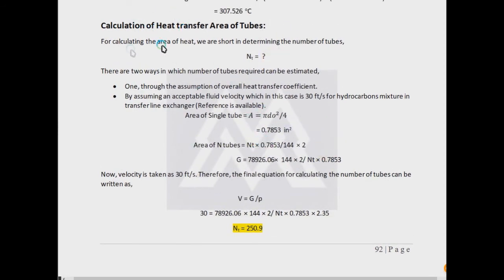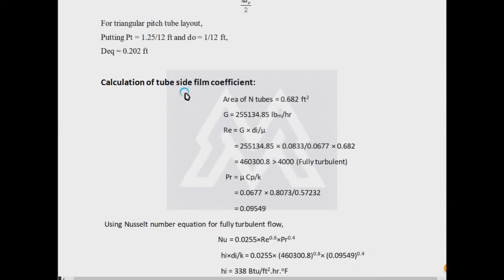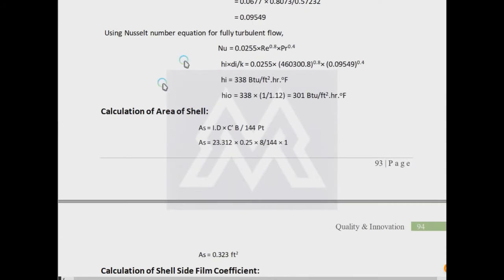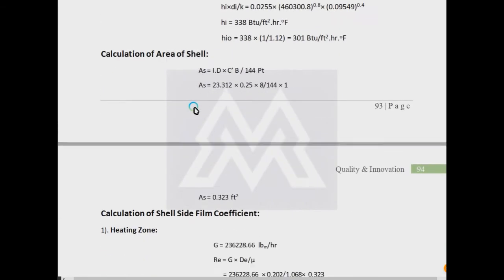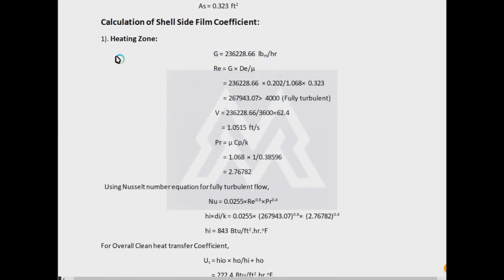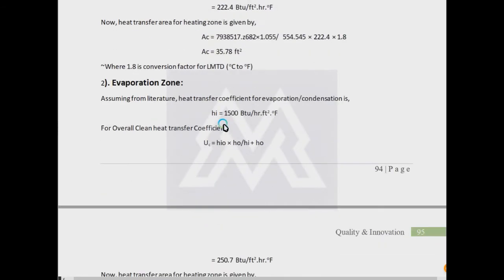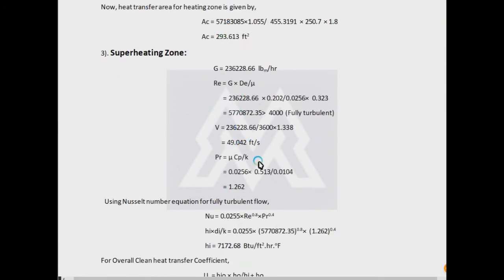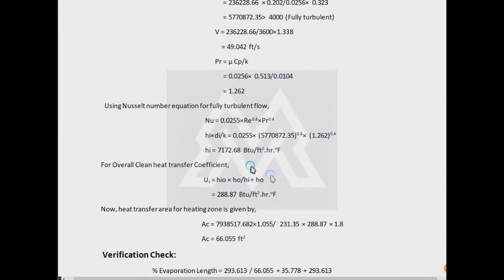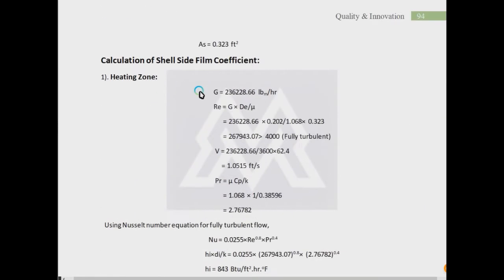Other things are the same, like calculation of heat transfer area of tubes and the shell equivalent diameter. But the second main difference is the calculation of the film coefficients. The film coefficients are also divided into three zones. The same procedures will be applied: mu Cp over k, density, everything will be different for the liquid water. Also in the superheating zone, the vapor density, viscosity, thermal conductivity will be used. Same procedure will be applied for the calculation of the heat transfer coefficient, and the overall clean coefficient will be calculated by fixing one tube side coefficient as the phase change is only taking place on the shell side.